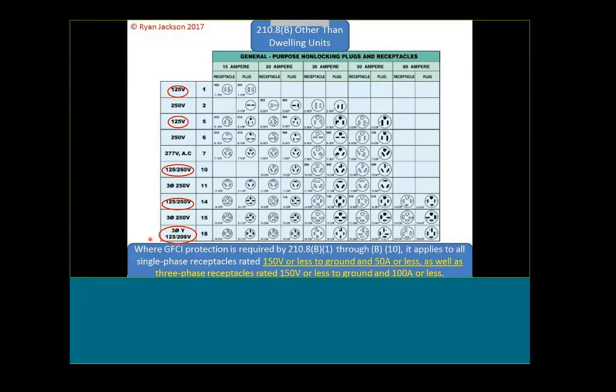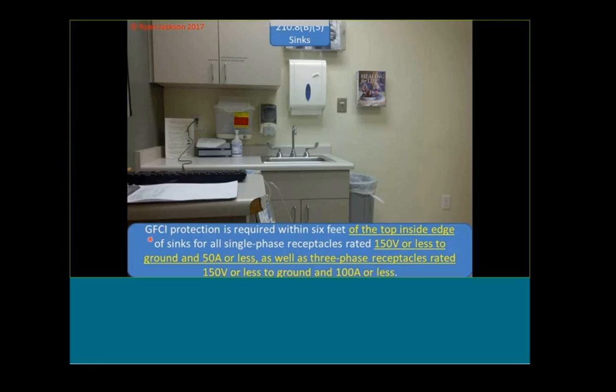Where the GFCI is required, it applies to all single-phase receptacles rated 150 volts or less to ground and 50 amps or less, as well as three-phase receptacles rated 150 volts or less to ground and 100 amps or less. That's showing a code change.